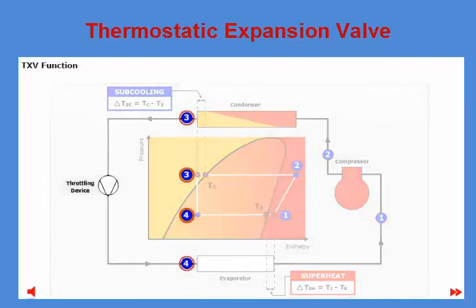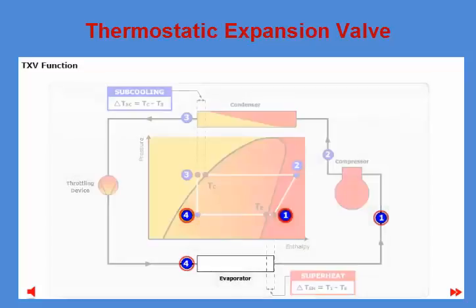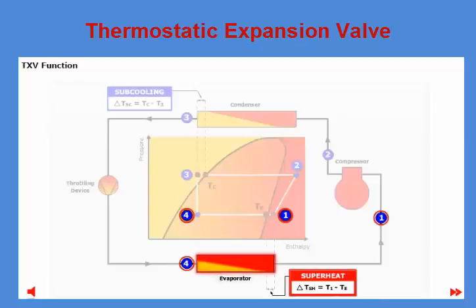Between points three and four, the liquid refrigerant expands because of the pressure drop in the throttling device, thereby dropping in both pressure and temperature. Refrigerant leaves the throttling device as a mixture of vapor and liquid at low pressure. Finally, between points four and one, the refrigerant is heated in the evaporator, evaporating the remaining liquid to vapor. Refrigerant leaves the evaporator as superheated vapor; pressure is not changed in the evaporator.